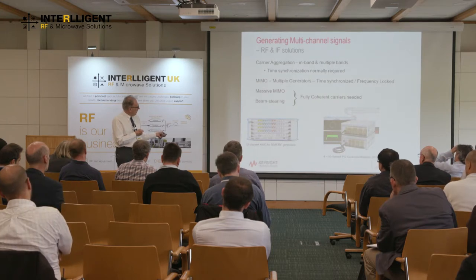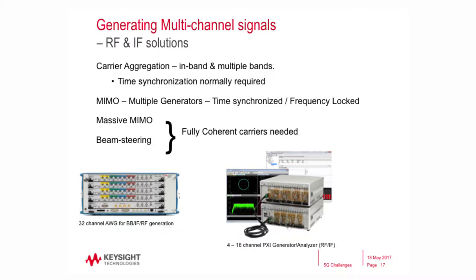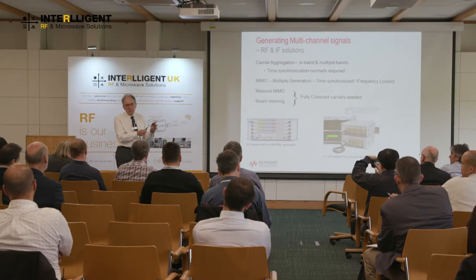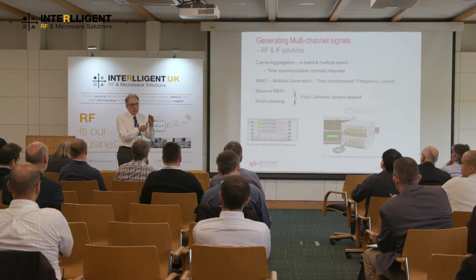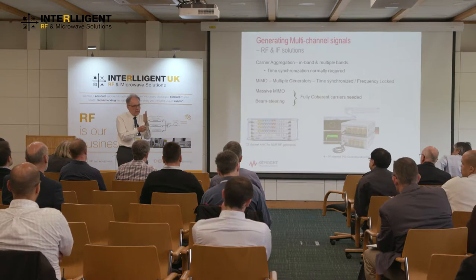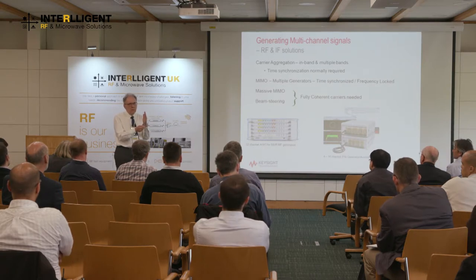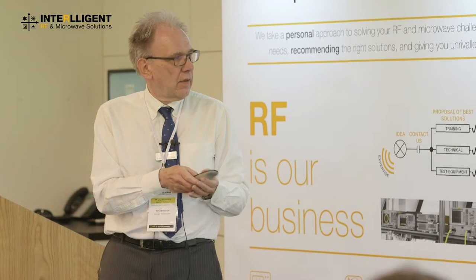One of the things we can do with this equipment is individually change the time delay of each one of these channels by a finite impulse response filter, which can have its coefficients changed in real time, running at our sample rate. So you can make very small changes to the coefficient taps to make very small time delay adjustments to those signals.